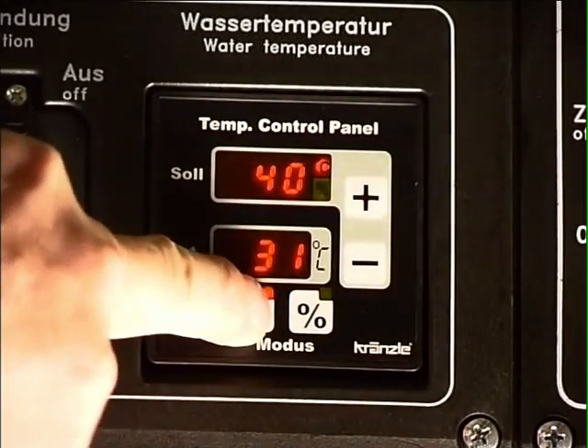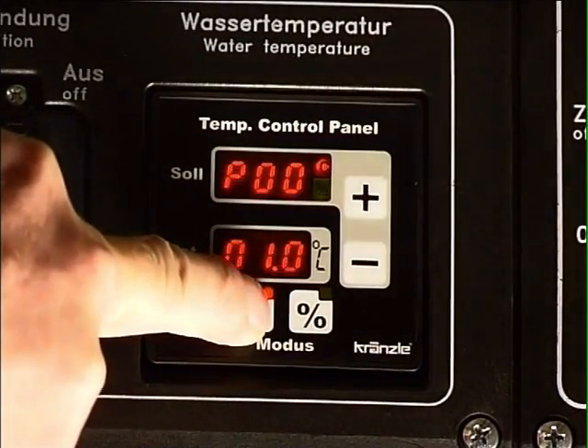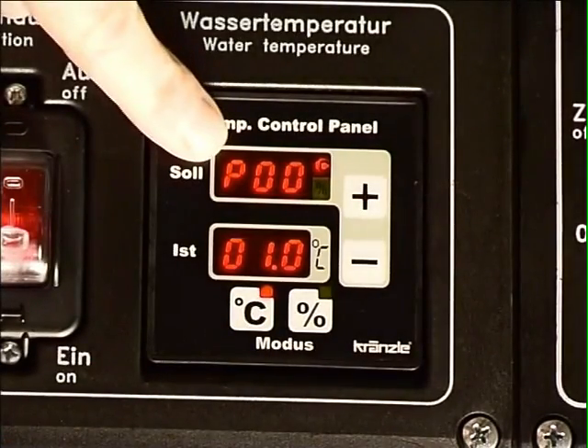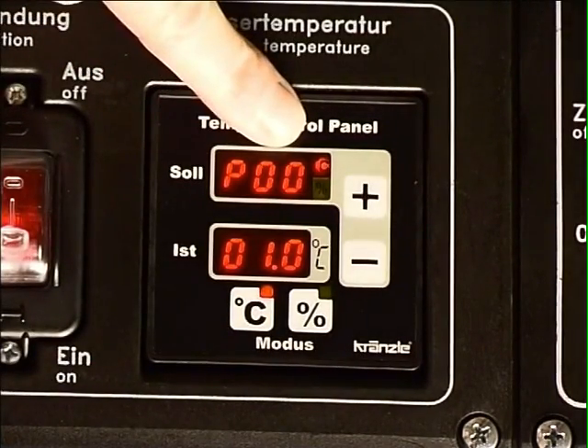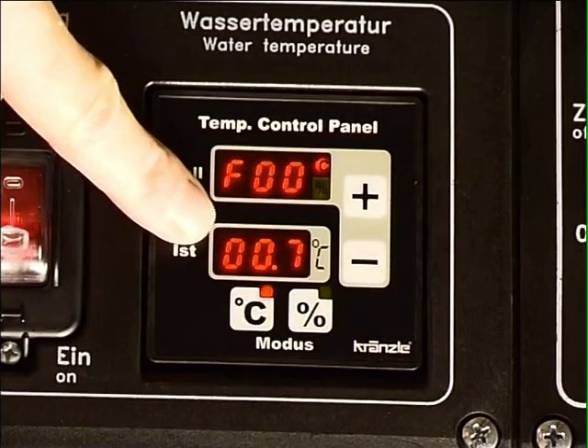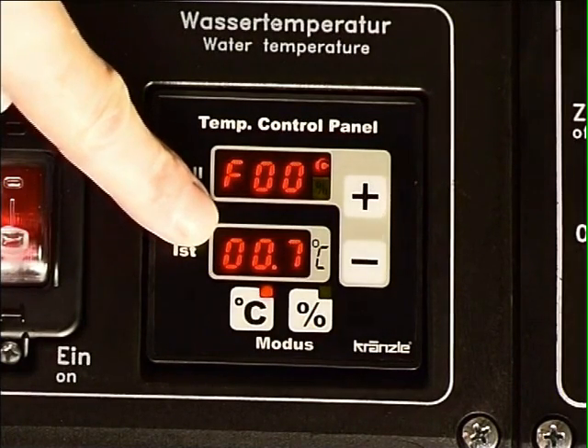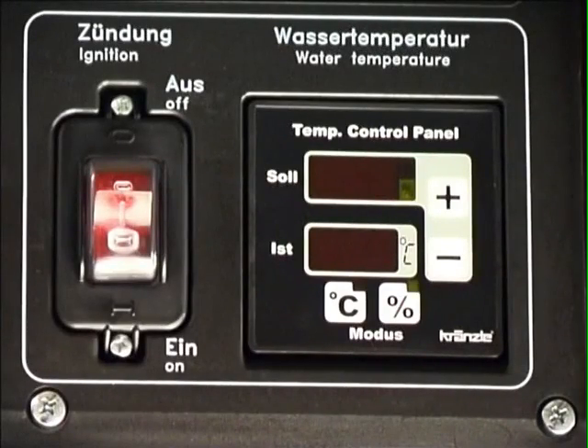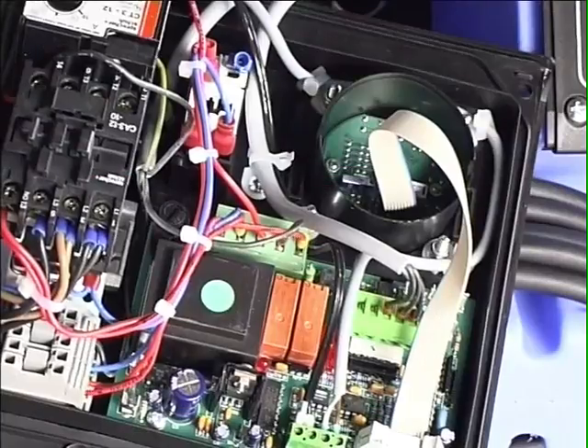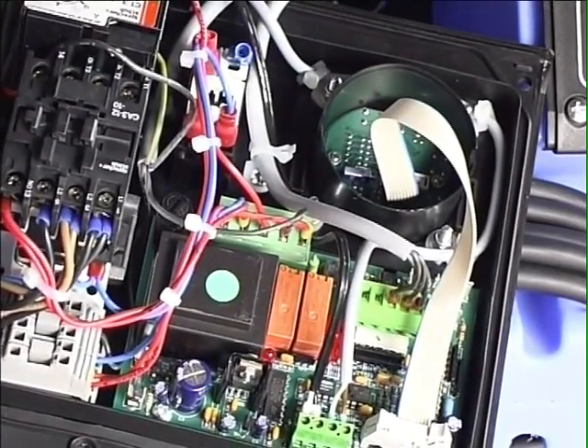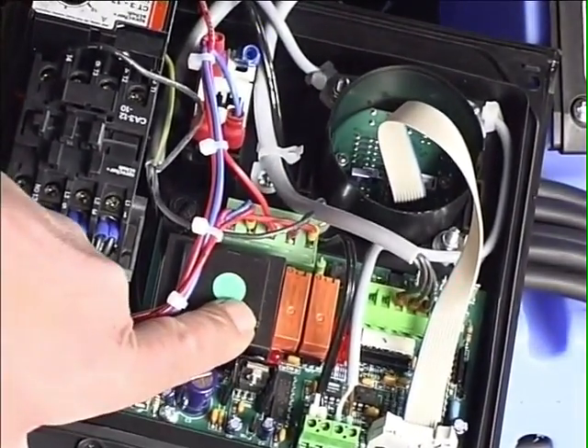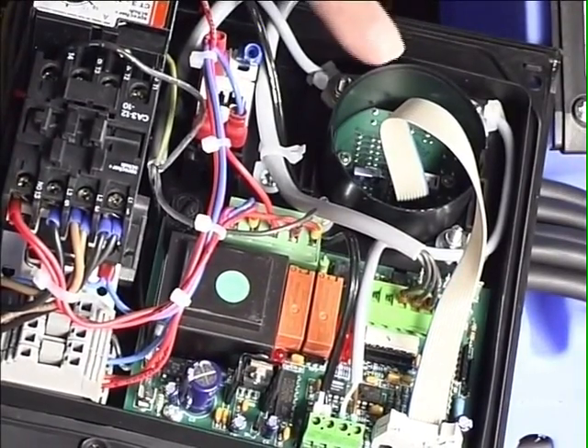You can also read operating hours of the pump with P, and of the burner with F, both new features. On request, you can deactivate the 20-minute safety switch off. Here you can find the circuit board of the new thermostat settings. And there is the display.